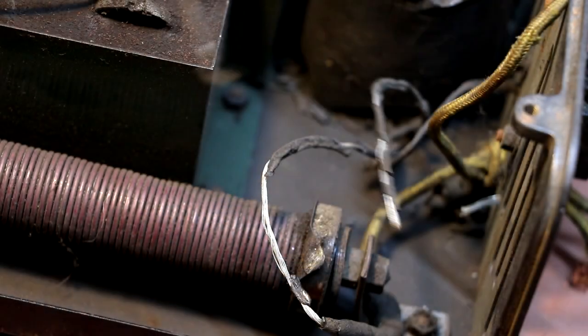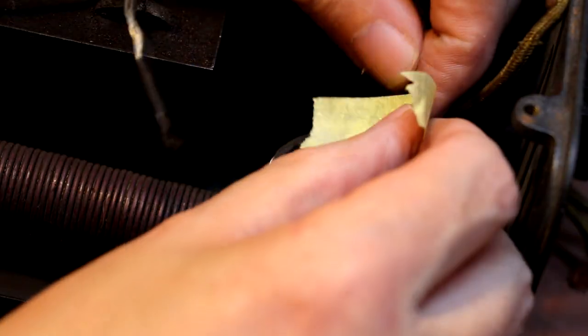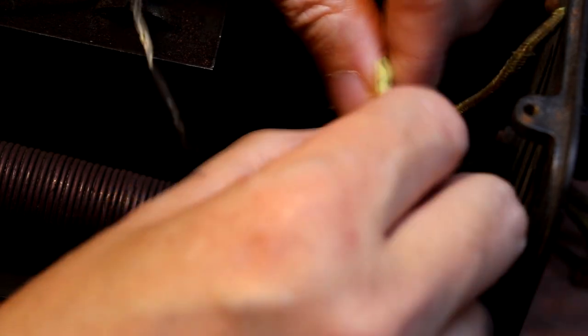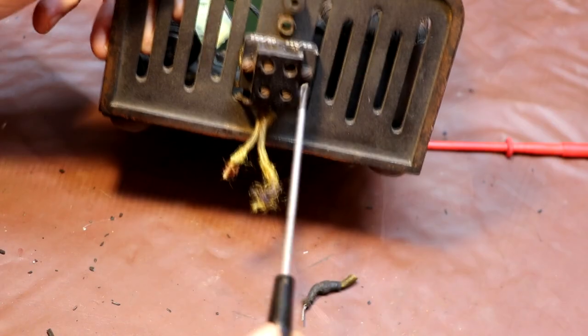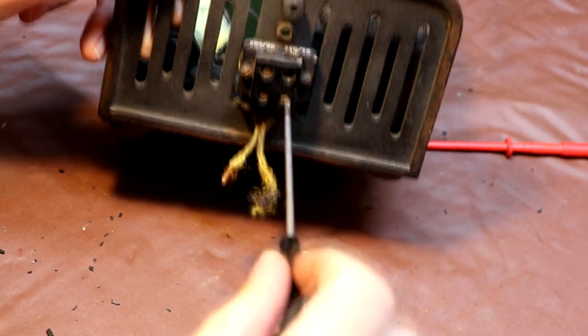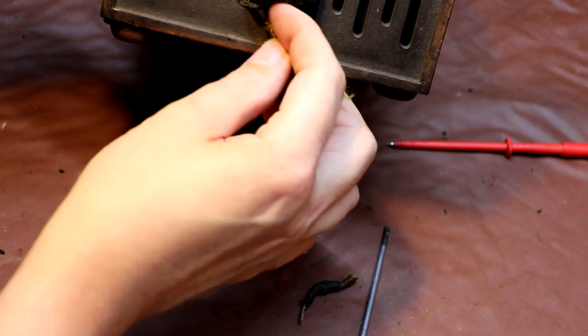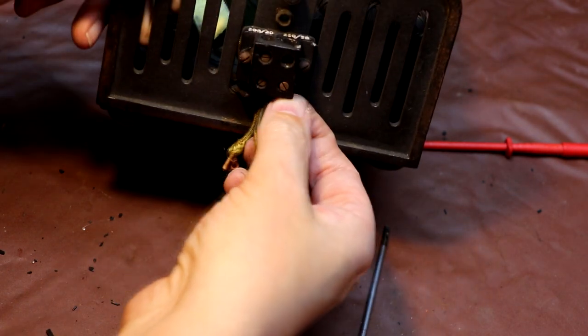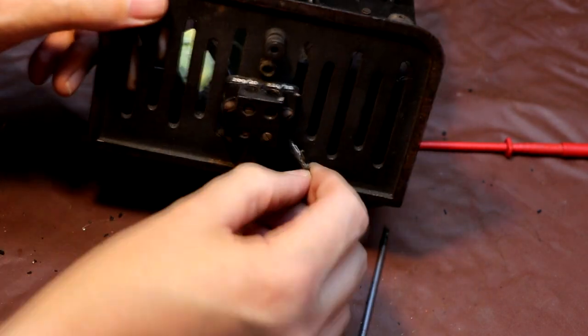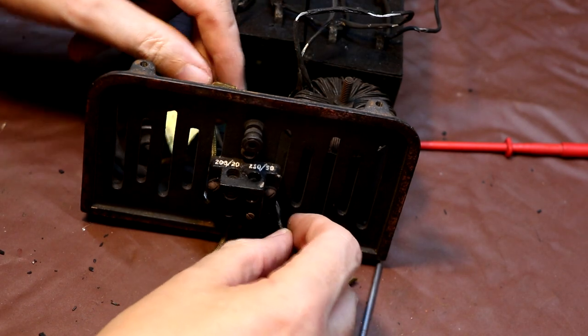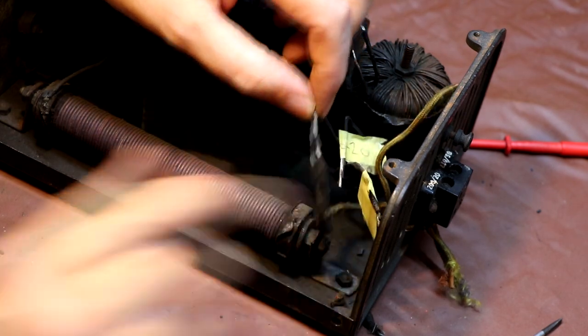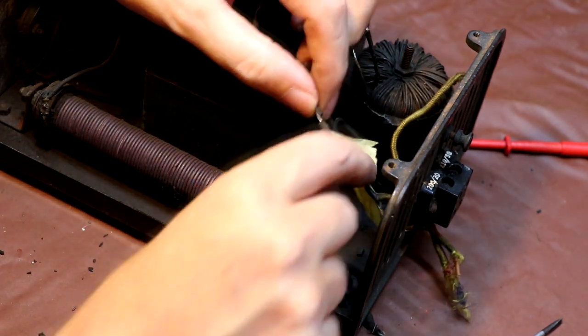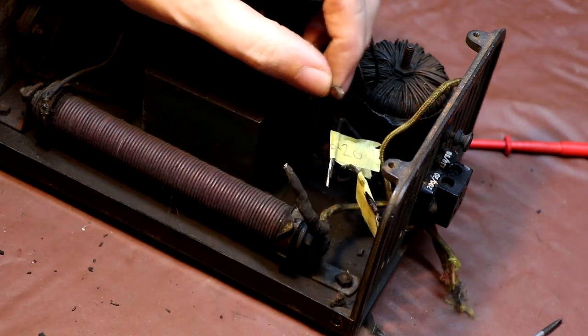So I'm going to cut off the 220 winding first. Let's just snip that off. You can see pretty much all the insulation is broken off it. So there's 220-20. Let's disconnect the other winding. And that one's 250-50. And then this is a live wire coming into it here. So we're going to cut that off.